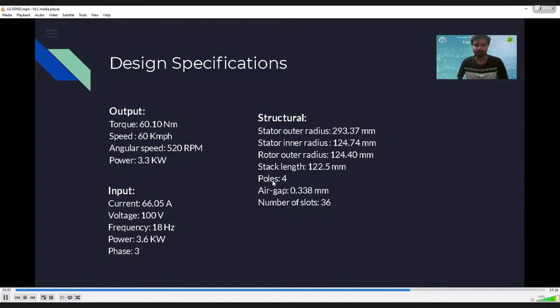Based on these output variables, we calculated our input. The voltage is kept at 100 volts, keeping the safety of personnel into consideration, and it is a three-phase motor. Based on these output and input values, we have designed a motor whose structural specifications are as follows: the stator outer radius is close to 294 mm, and the air gap is 0.3 mm. The number of slots in the stator is 36, and the number of poles is 4.